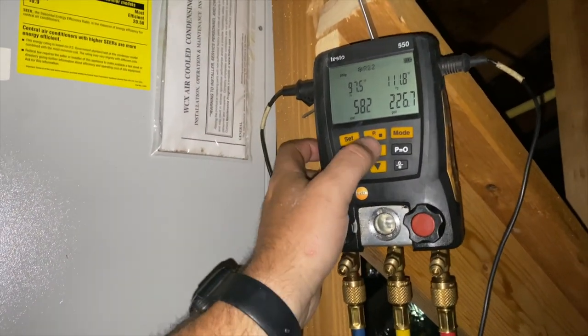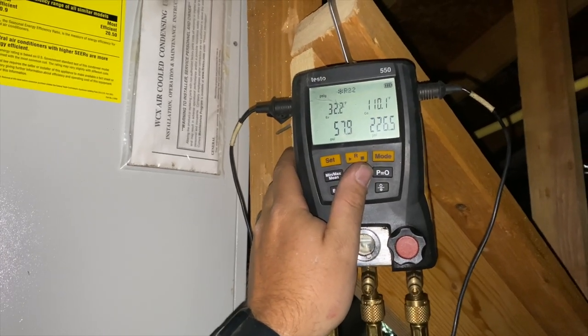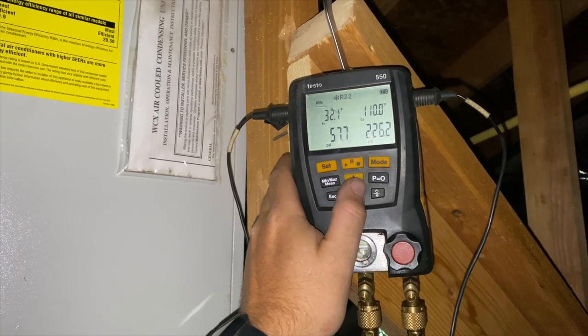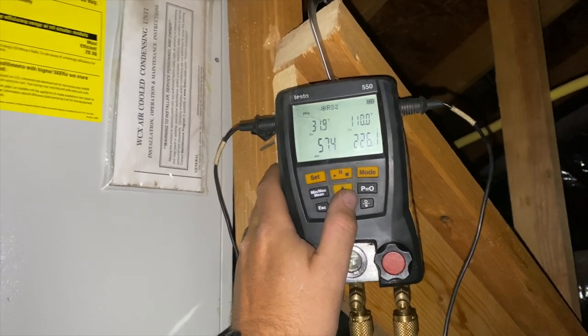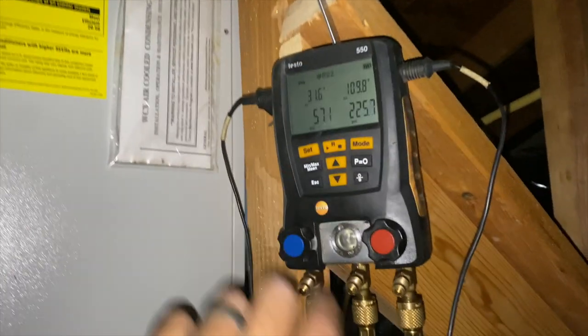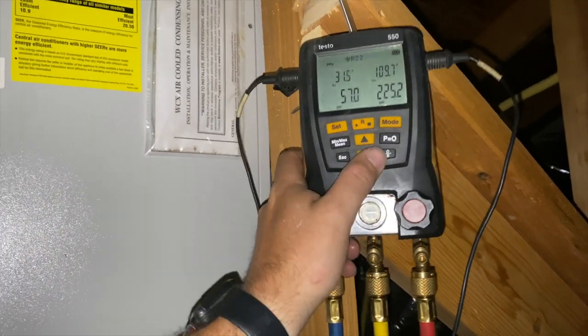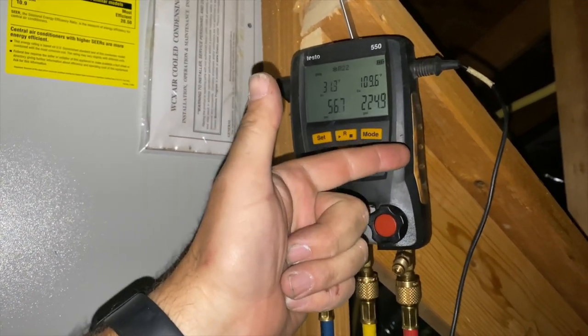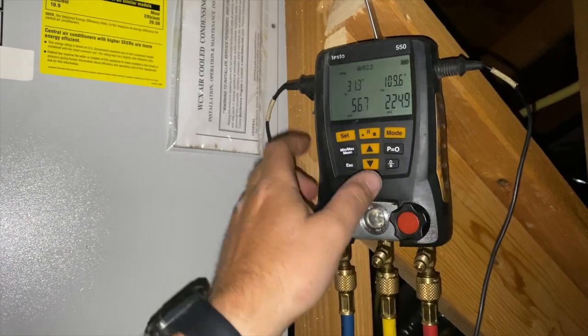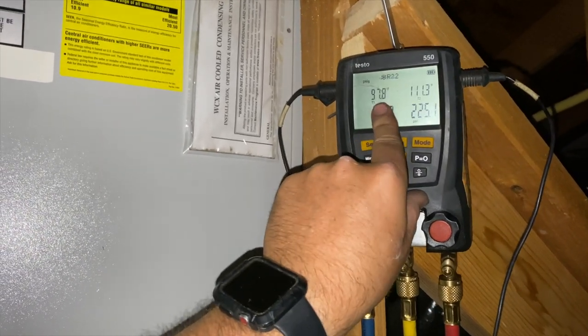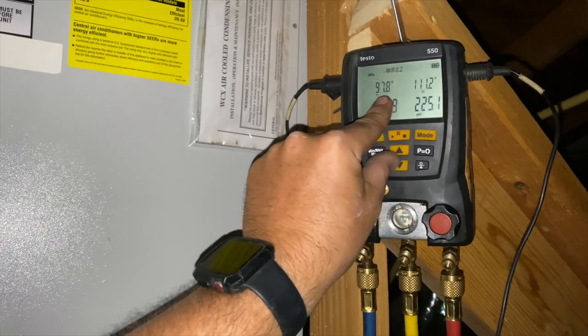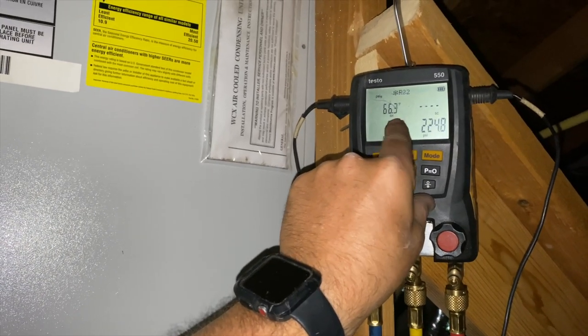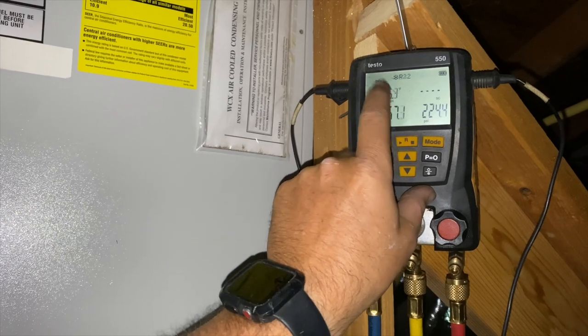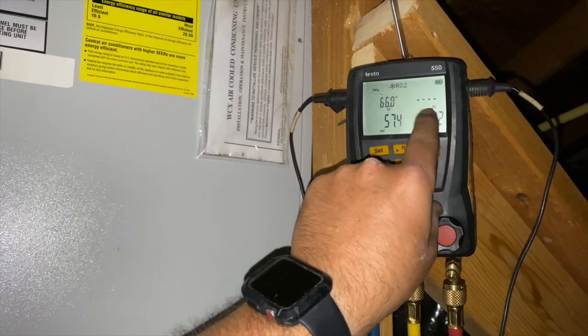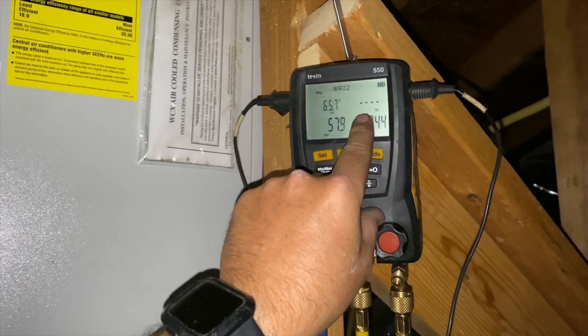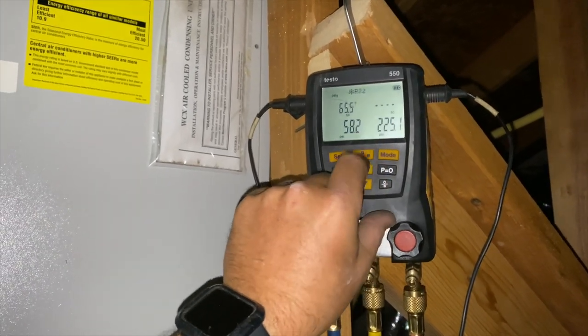Okay, so here's where we're at. We have a suction of 57-ish, a high side of 226, which is actually high because our current ambient temperature is 75. So 75, 85, 95. So it's slightly high, but look at our suction temperature. And then look at our superheat, super high, so we are low, and our subcooling is completely negative. When it's negative on this unit, it just goes blank.